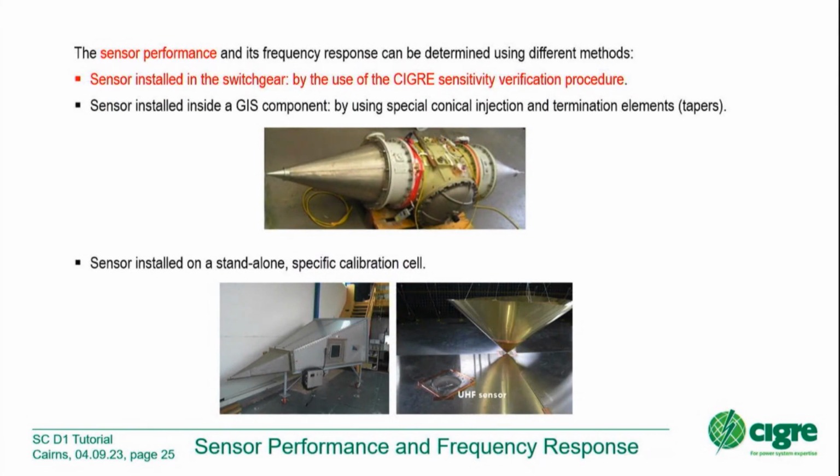In this working group, we discussed really heavily how to deal with the sensors and the electronics and PD instruments. Should we look for standardization of each device by itself? At the end of the study, we said no, that's not important. We will look for the complete measurement chain.